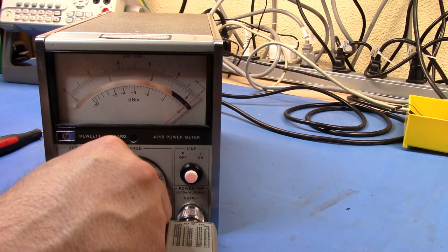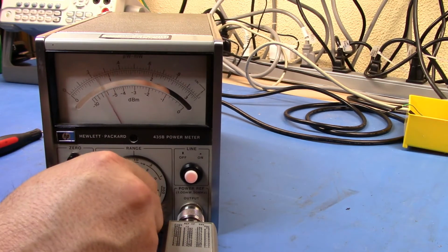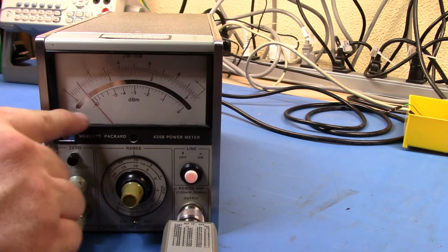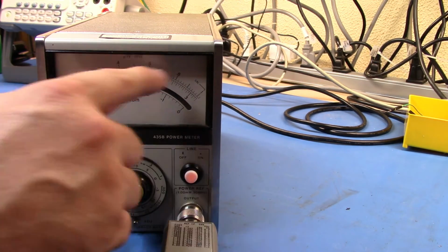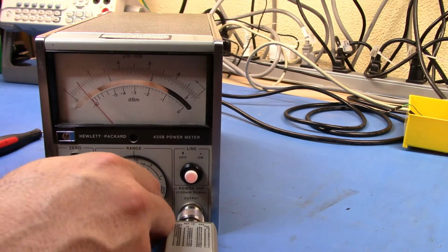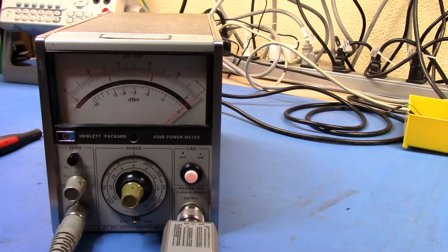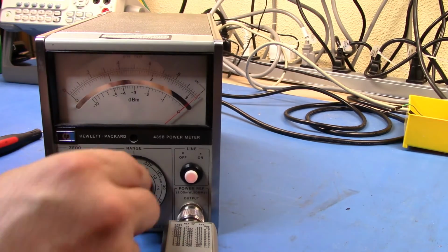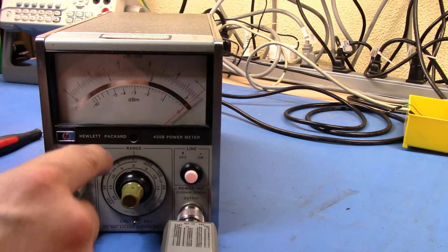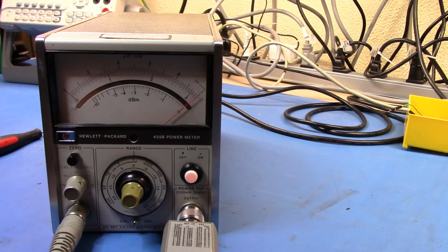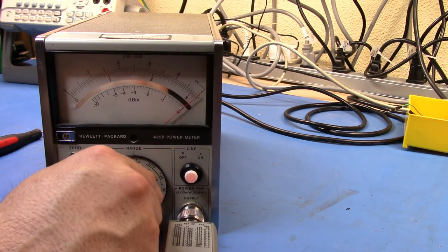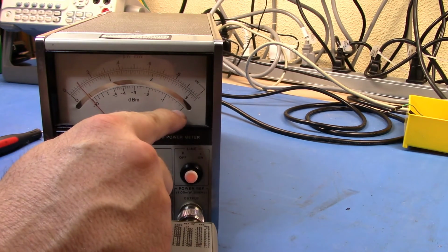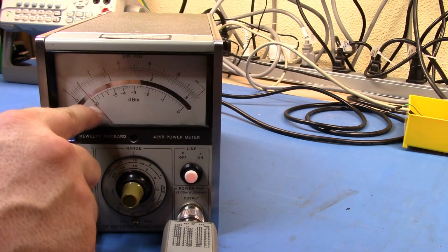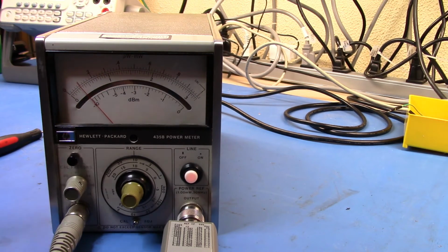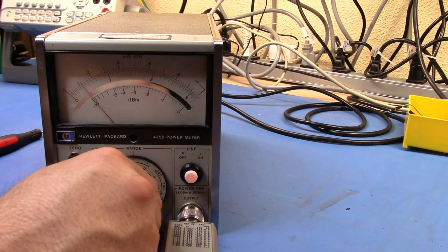So if I go to 3, you'll see that it's there. If I go to 10, you'll see that it's at 1 effectively across the top there. It's at 0 over here, so I can do 0 dBm and an offset. On the 10 dBm range, that would be 10 dBm, and down here you can see that I'm reading minus 10 dBm, so it's saying that I'm off there by a bit.